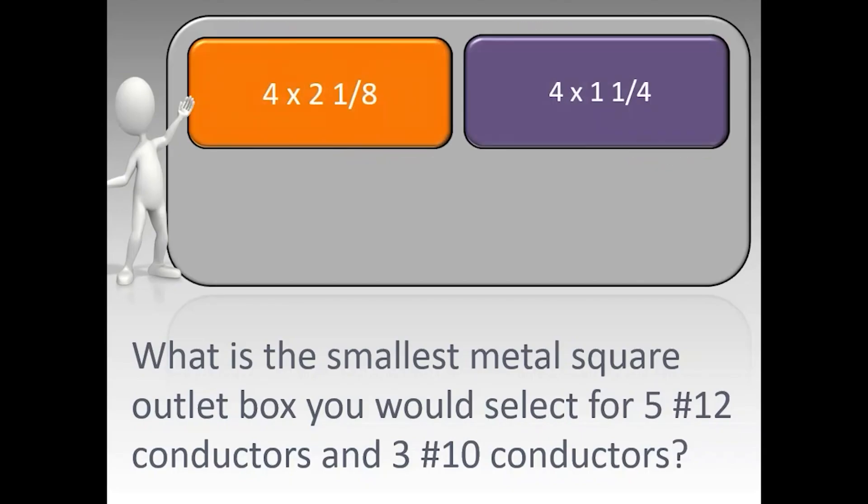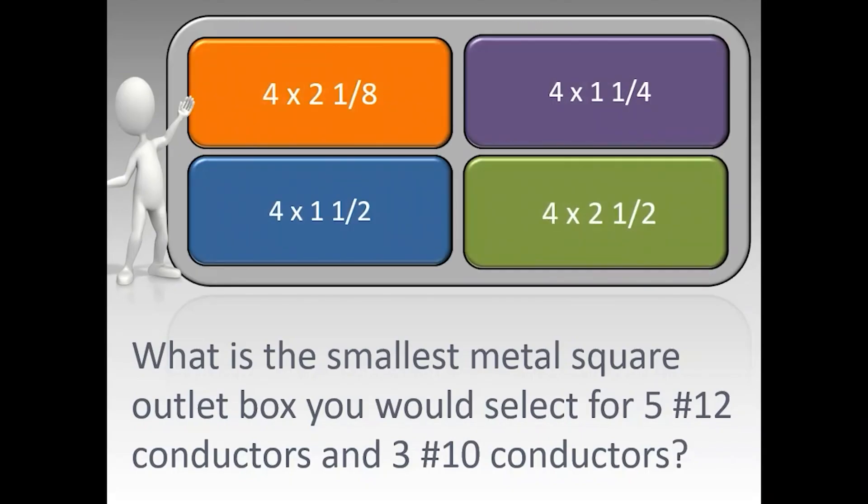What is the smallest metal square outlet box you would select for five number 12 conductors and three number 10 conductors? The correct answer is a four by one and a half.